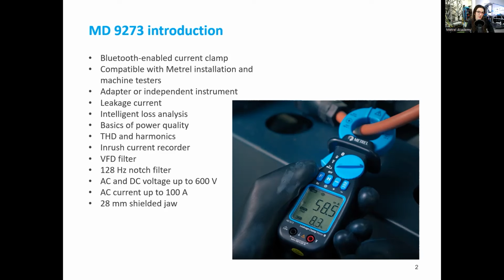So what are these supported measurements in the MD9273? Already the name mentions the leakage current ability. So we can reliably measure currents from about 10 microamperes upwards. While measuring low currents in about milliamp range, the clamp can sense the losses in the system, and it can predict the source of those losses. So are we talking about nonlinear loads, about the insulation losses, or the combination of the two? The clamp jaw is shielded, and therefore it's very resistant to environmental disruptions.